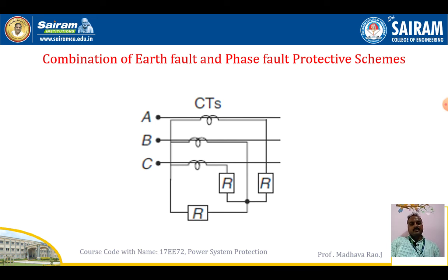This scheme is more popular than the other two schemes, since we can protect the equipment from both faults, earth fault and phase fault. The fault which involves the ground and the fault which does not involve the ground, we can protect against both faults. Here in all the cases, wherever the relays are used for earth fault and phase fault, those relays belong to overcurrent relays.